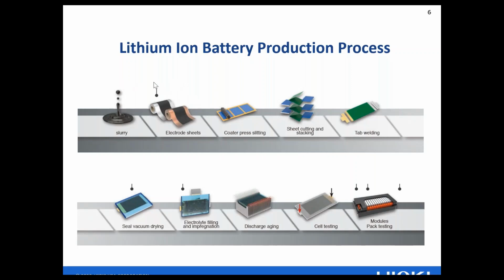What I'm concentrating on in this presentation is the first and the second step. The reasoning here is that the earlier you detect issues with your material, with the electrode sheet specifically, the earlier you can make sure that your final product is not going to get shipped. Meaning you save a lot of money in sorting out bad sheets early on in the process versus trashing the whole module at the end of the production line. That's what this talk is going to be about. So mostly talking about research, development, and production testing, incoming inspection.